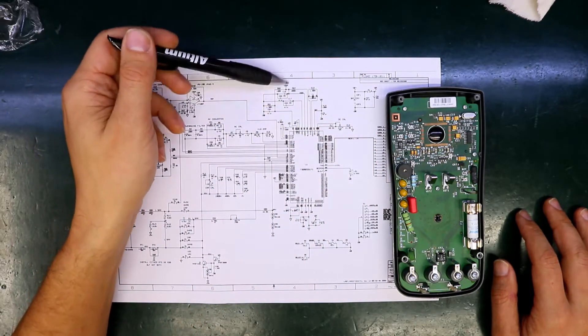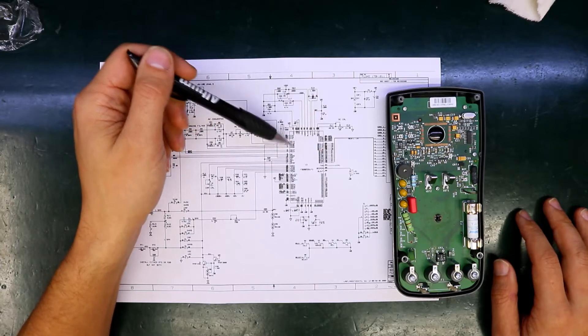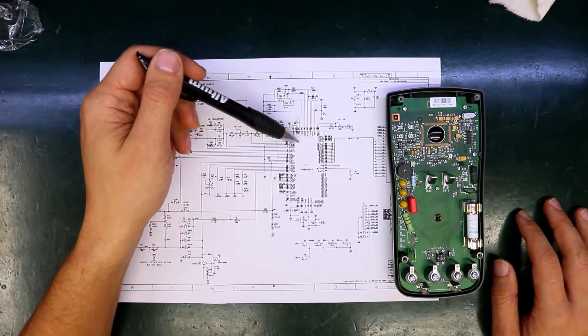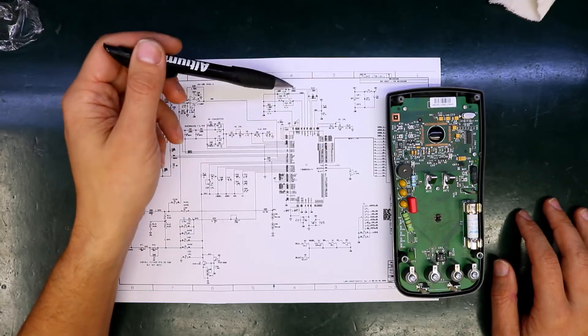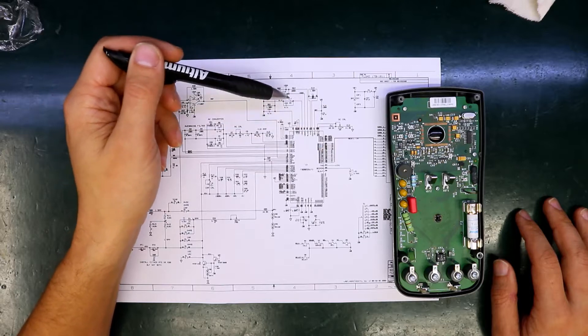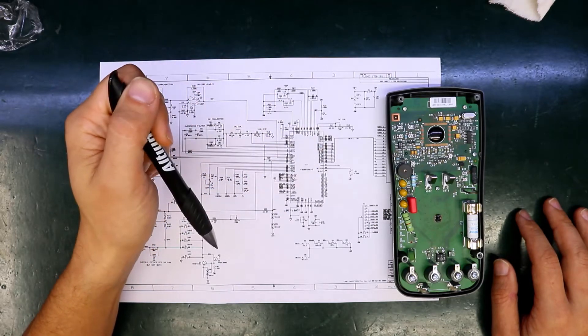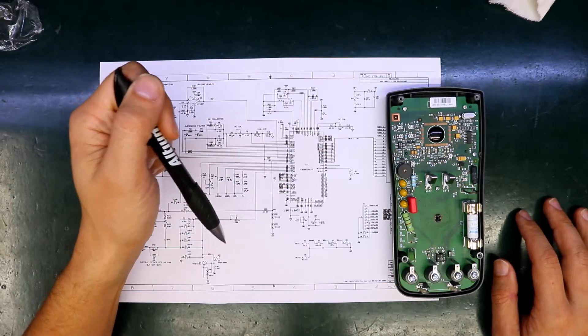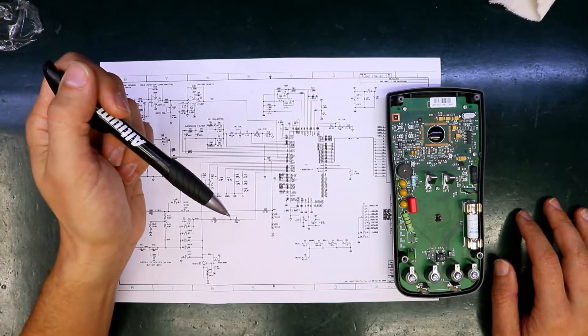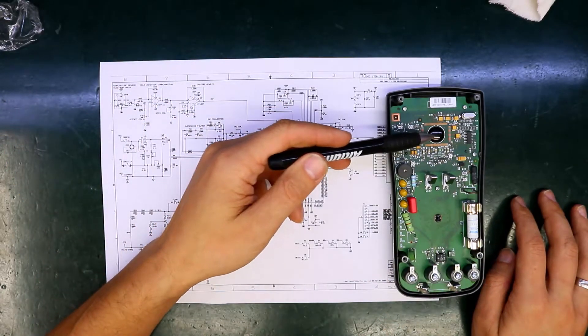Also there are two analog voltage outputs — probably there are internal DC-to-DC converters — but they also seem to be dead. This is the case where I think the entire chip is broken and I need to find a new one-chip solution and try to find a way to replace it, because as you can see it is chip on board.